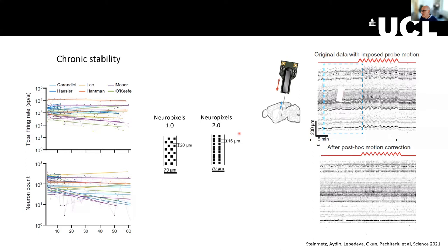Another change is the arrangement of sites on the shank, which is now linear. This might seem like a small difference, but besides tighter spacing, it allows us to undo brain movement much better, thanks also to improved software. To demonstrate this: we first have the natural movement of the brain relative to the probe, and then the probe is deliberately advanced in and out rhythmically. Using this geometry and software, we're now able to undo this motion — both natural brain motion from breathing and heartbeat, and imposed motion.